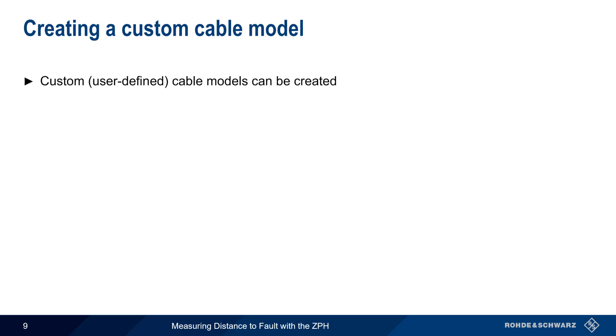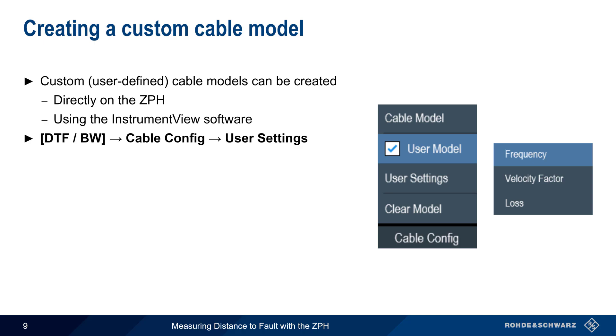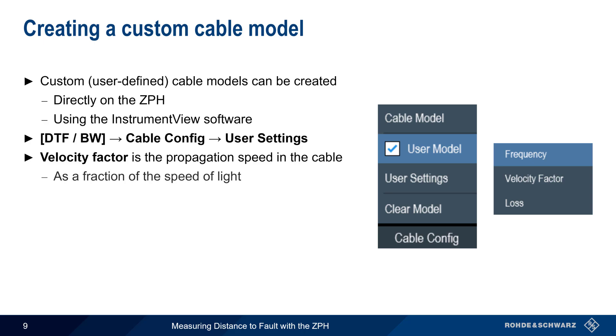It's also possible to create a custom or user-defined cable model. This can be done directly on the ZPH itself, or it can be created on a PC using the free Instrument View software. To create a cable model on the ZPH, press DTF Bandwidth, Cable Config, and User Settings. There are three configuration parameters. Recall that velocity factor describes the speed of propagation in the cable, which is specified as a fraction of the speed of light. Typical values are either 66% or, less often, 82%.